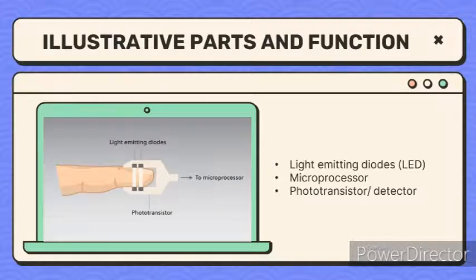Now let us see the different parts of the pulse oximeter and their functions. In the upper part of the pulse oximeter, you will see a red light, which is the light emitting diode or the LED. This shines red and infrared light through the fingers. In the middle part is the microprocessor, which measures the changes in the wavelength and absorbance of the light in the arterial blood. In the bottom part of the oximeter is the phototransistor, or the detector, which releases the information to the microprocessor.